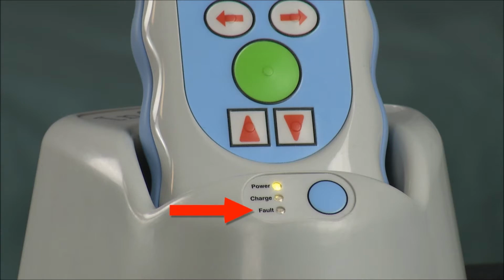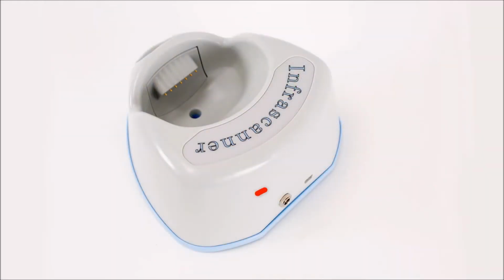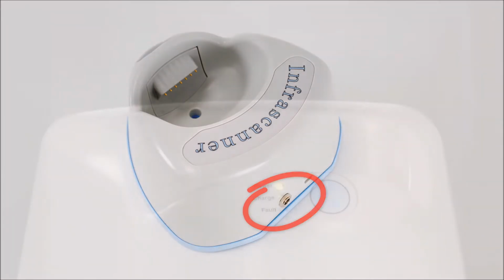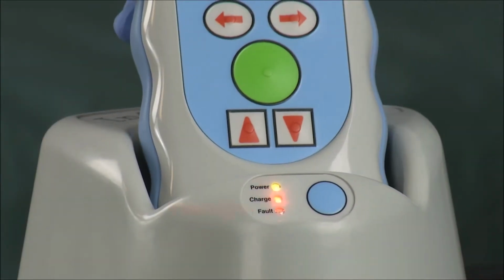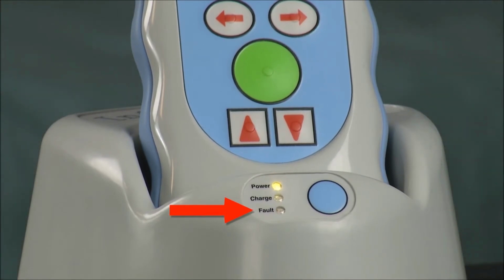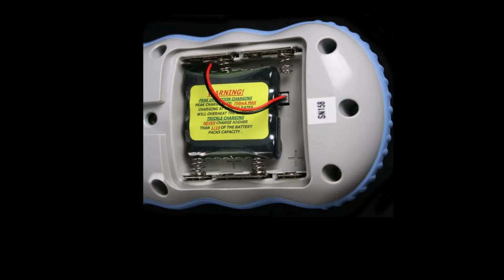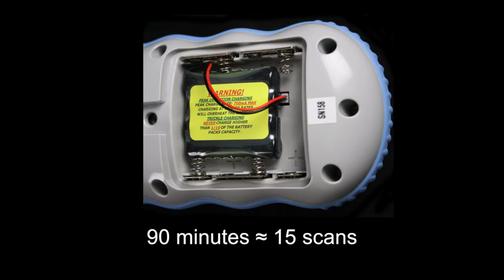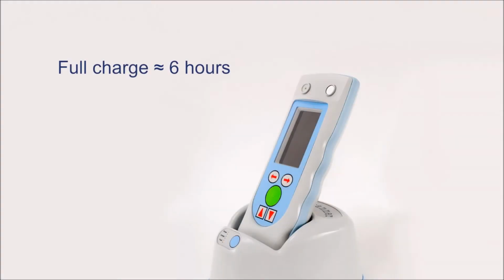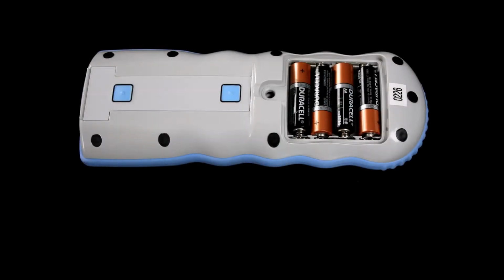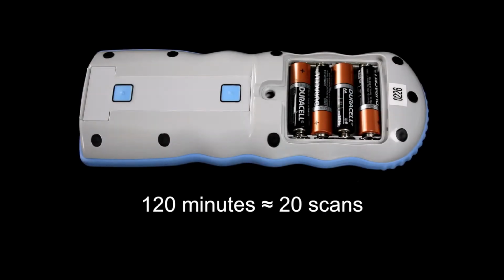When the red fault light is on, there is a problem with charging. Try removing the unit and unplugging the cradle. Plug the cradle back in and place the unit back in the cradle. If the red fault light persists, please contact Infrascan customer support. When running on the rechargeable battery pack, the Infrascanner will operate for 90 minutes, taking approximately 15 scans. It takes approximately 6 hours to fully recharge the battery. If AA batteries are used, the Infrascanner will run for 120 minutes, taking approximately 20 scans.